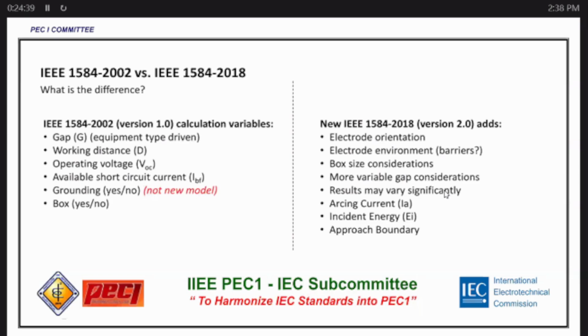So that's the picture I showed earlier, the electrode, if it is oriented vertically or horizontally. We know that if your orientation is vertical, when it explodes it goes downward, but if your orientation is horizontal, when you open the panel, it will really hit you directly. That's where the strongest effect is and the biggest danger to people. We also considered barriers, box size, and the gap, and the result may vary significantly.